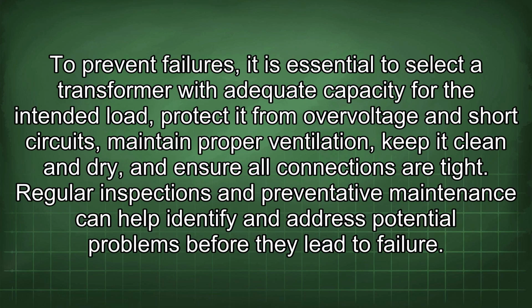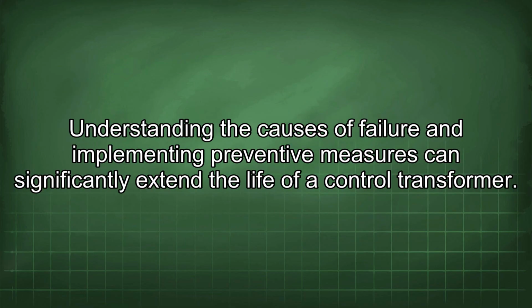To prevent failures, it is essential to select a transformer with adequate capacity for the intended load. Protect it from overvoltage and short circuits, maintain proper ventilation, keep it clean and dry, and ensure all connections are tight. Regular inspections and preventative maintenance can help identify and address potential problems before they lead to failure. Understanding the causes of failure and implementing preventive measures can significantly extend the life of a control transformer.